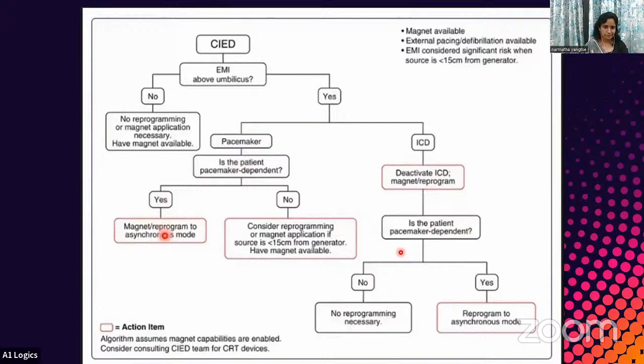But if there is a chance of electromagnetic interference less than 15 centimeters, then you have to do the magnet application or reprogramming. Okay, now if the patient is having an ICD, definitely if there's an ICD, you have to deactivate the ICD. Then see next whether the patient is pacemaker dependent. If he is pacemaker dependent, then you reprogram to the asynchronous mode. If not, then no reprogramming is necessary. So this is the emergency protocol. You have no time for any evaluation.